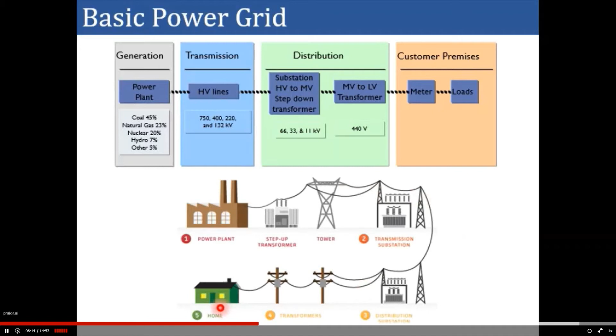Now, how do you monitor and control power at the transmission level? We utilize a supervisory control and data acquisition system, called SCADA. Let's see the architecture of the SCADA system. At the substation level we have a device called the remote terminal unit (RTU), and we also use PLCs, that is programmable logic controllers.